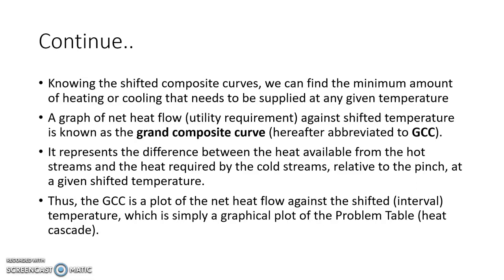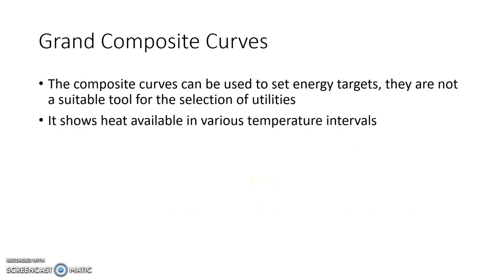A graph of net heat flow — that is, the utility requirement of the cascade — against the shifted temperature is known as the Grand Composite Curve. In the Problem Table Analysis, the last column shows the net heat flow starting from minimum hot utility to minimum cold utility, with a zero in between indicating the pinch point, as a function of shifted temperature in the first column. Plotting that gives the Grand Composite Curve or GCC. It represents the difference between heat available from hot streams and heat required by cold streams relative to the pinch point at a given shifted temperature.